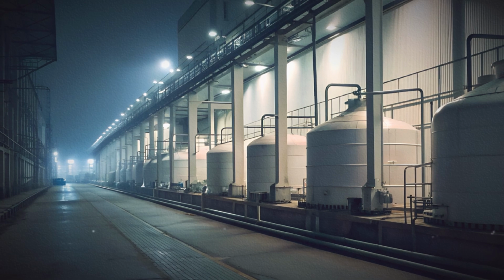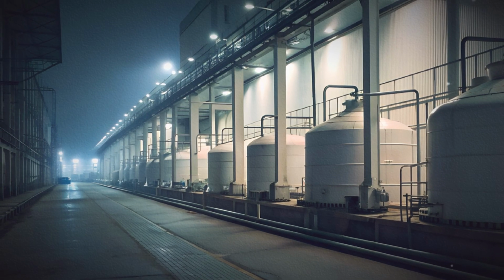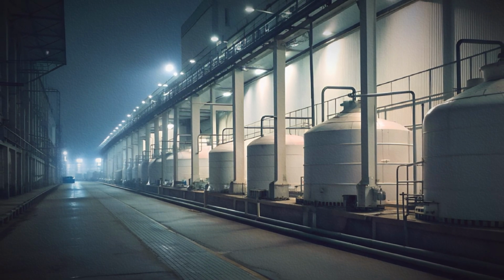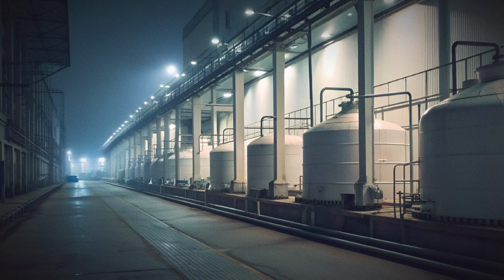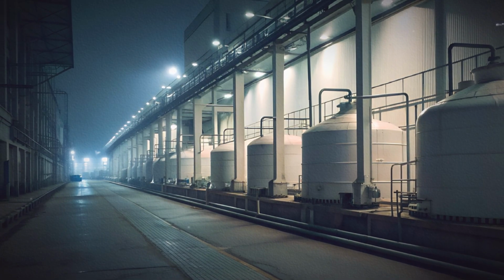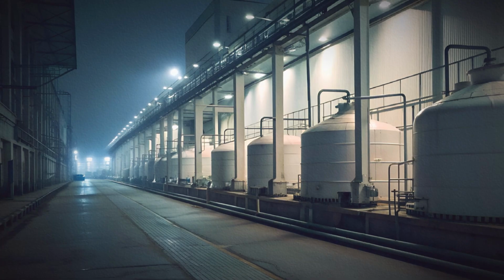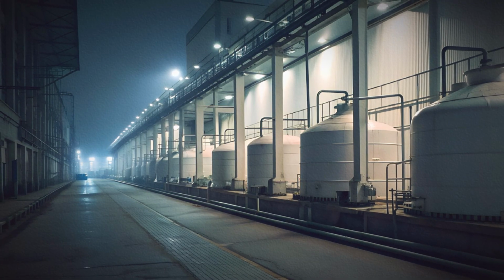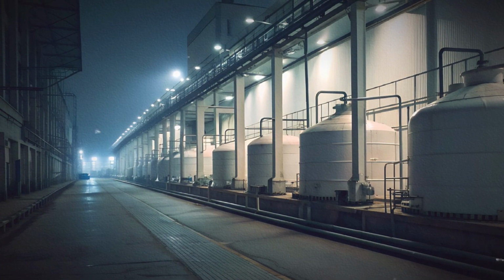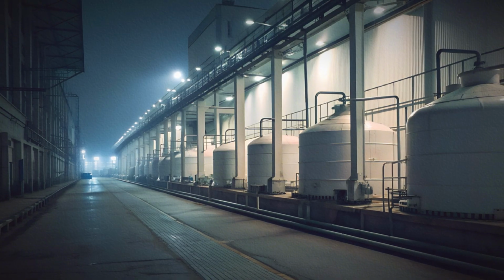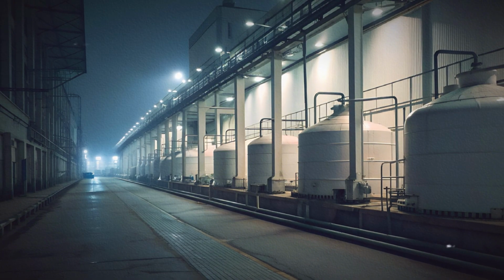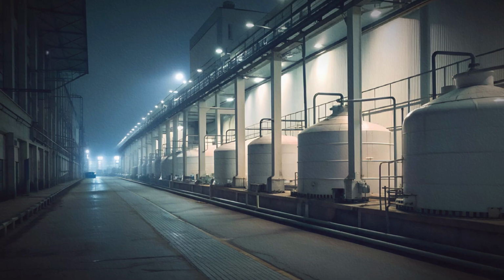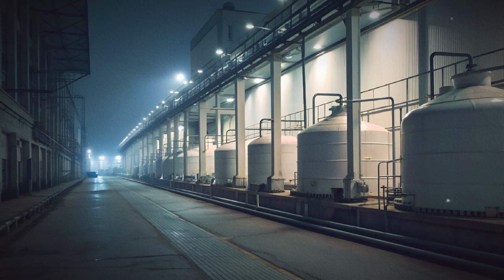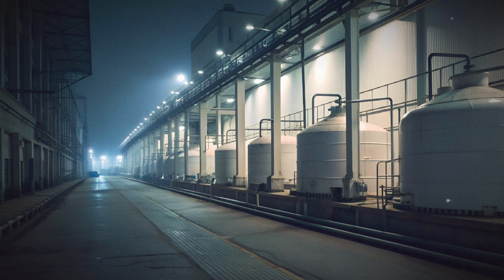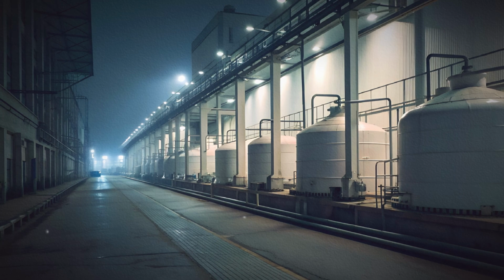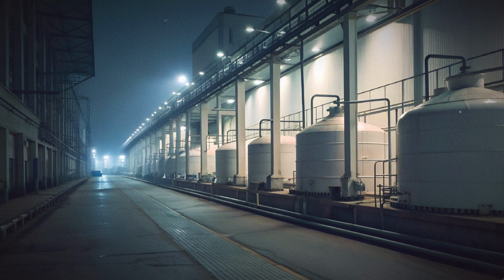Multimedia filters are a variant of granular media filters. They use at least two different materials in distinct layers. A common configuration places anthracite at the top, a layer of sand below it, and a layer of finer sand or garnet at the bottom. Anthracite particles are relatively large and have lower density. Sand particles are smaller and denser. Garnet or other heavy media at the base provide fine support and prevent media loss to the underdrain.